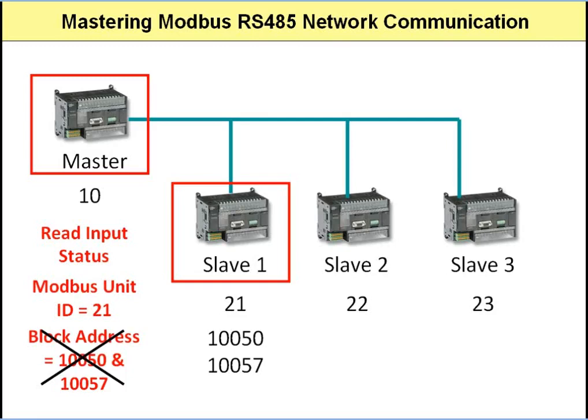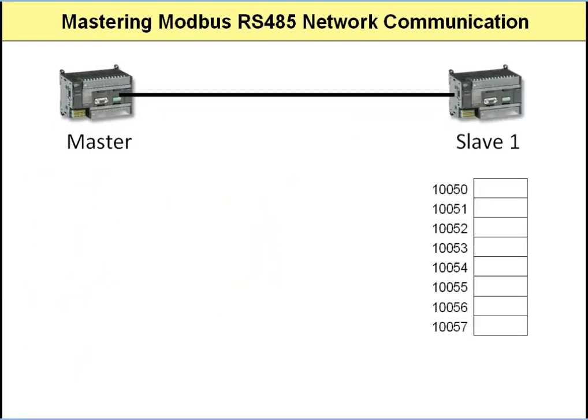Here's where Modbus is a little different from many other protocols. We're concentrating on these memory block addresses 10,050 and 10,057. What we'd like to do is simply specify those two addresses, send the message to the slave, and have the slave respond back with the data at those two memory blocks. This diagram shows our example with the master and slave, and gives a representation of some of the memory blocks of the slave in the inputs area.